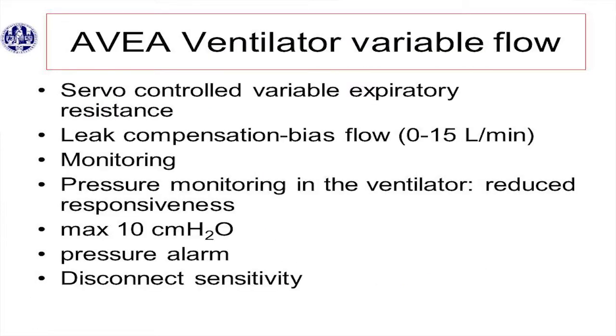The AVEA, which we use, as already said, is servo controlled. There's a leak compensation bias flow up to 15 liters per minute. You can monitor. The problem is you do the pressure monitoring in the device, so there is some delay and reduced responsiveness. And there's a max of 10 centimeters of water. It will give you an alarm when there is disconnection.